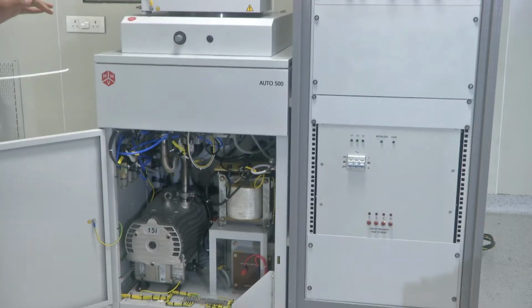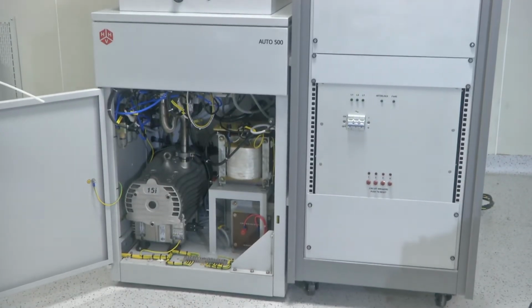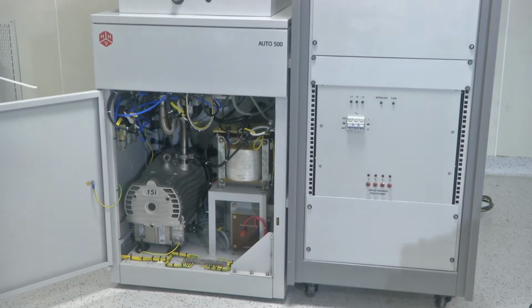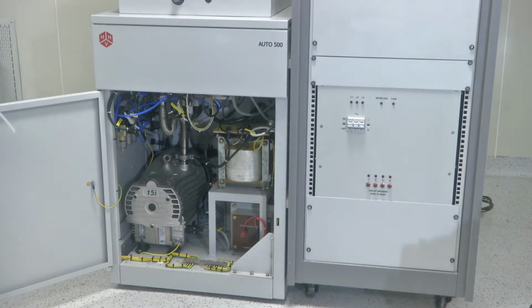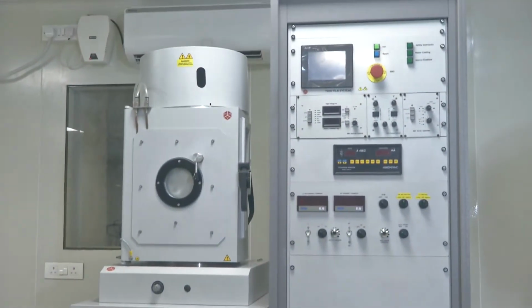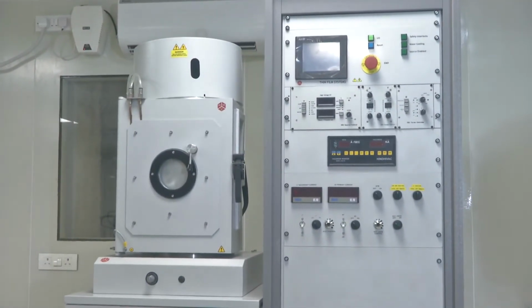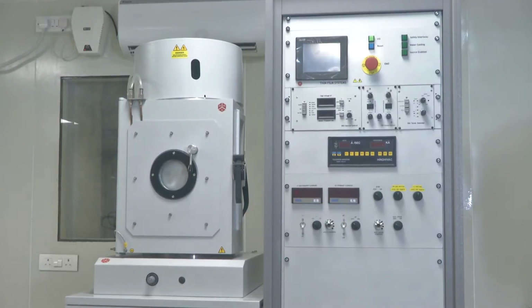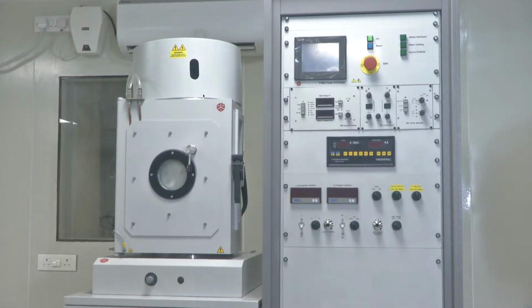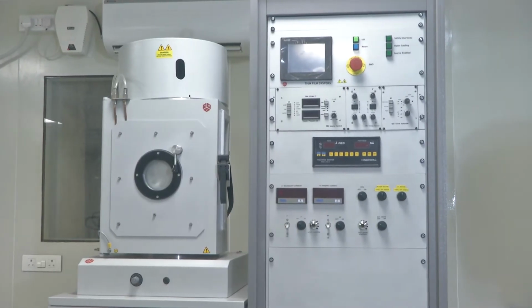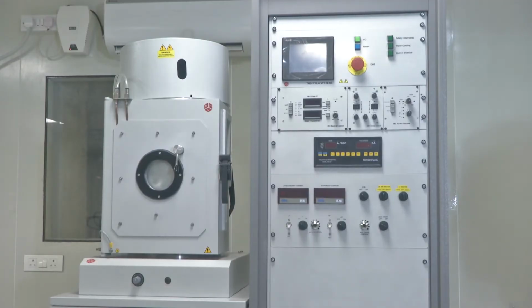After achieving a certain vacuum, all are electro-pneumatic valves, not butterfly valves. For operating any valve, compressed air is needed. On the control panel, you have individual switches: backing, roughing, high vacuum, and vent. These are toggle switches. When you switch one on, the valve automatically opens.